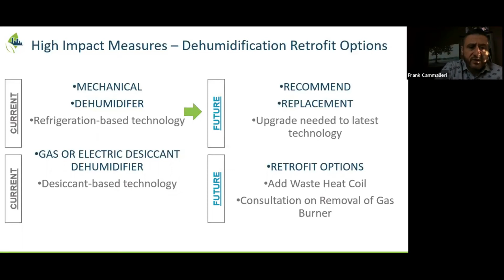In the case where there is a gas or electric desiccant dehumidifier, which is the case with the actual participant, there are some options that you can do with retrofit, which could be adding a waste heat coil or the removal of gas. Specifically for this participant, the existing equipment's at the end of life. But when we find certain sites that have dehumidifiers that have a bit of life left, there might be this option of adding a waste heat coil if it doesn't exist, to try to recover some of that heat.